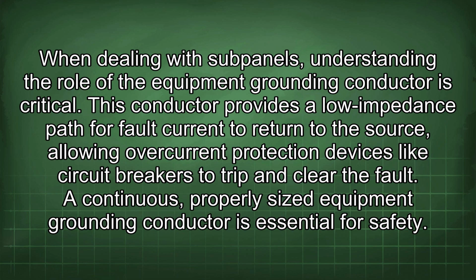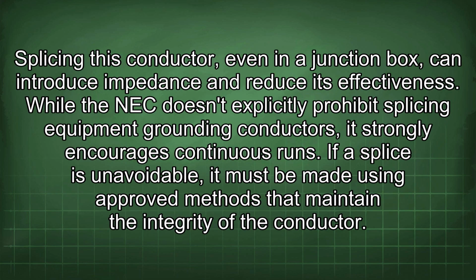This conductor provides a low impedance path for fault current to return to the source, allowing overcurrent protection devices like circuit breakers to trip and clear the fault. A continuous, properly sized equipment grounding conductor is essential for safety. Splicing this conductor, even in a junction box, can introduce impedance and reduce its effectiveness.